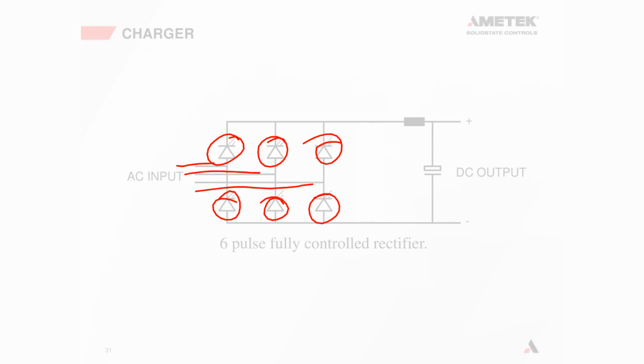So how does the battery charger do it? Well, every parameter, remember, is dictated by the battery, as I mentioned before. So what we do is we use a 6-pulse fully controlled rectifier. And when we say 6 pulses, it means we have 6 SCRs in our bridge. Okay, and we take our 3-phase input here and we convert that into DC, depending on the battery. And remember, for a lead acid battery, the nominal cell voltage is 2 volts. For a NiCad battery, usually the nominal stipulated voltage is 1.2. For lithium ion, it can be anywhere between 2.4 and 3.8.